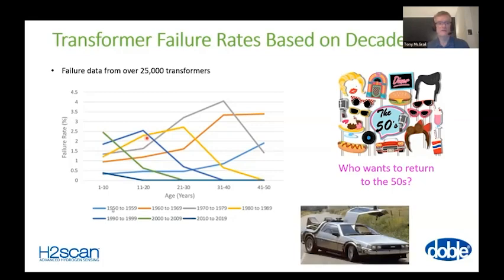But take it for what it's worth — these statistics are for the population, and we always have to remember that statistics apply to the population and not the individual. So if I have a transformer from 1985, to work out what condition it's in, I have to go look at that individual transformer: test and assess, gather the data, analyze, work out what failure modes may be in operation, and then determine the urgency of intervention and how long I think this unit has. Likewise, if I have one from 1990 to 1999, I may expect the population to show some will likely fail sooner, but to find out about an individual unit, I need to look at that individual unit. That, to me, is the important message: statistics apply to the population, not the individual.